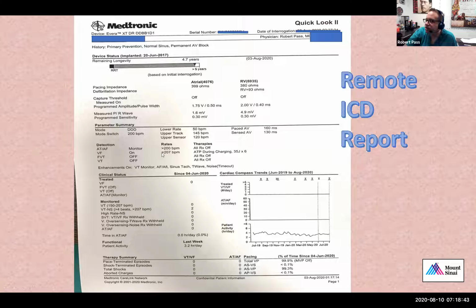But if the patient's heart rate exceeds 207 beats per minute, the device will try anti-tachycardia pacing, which is where the device will try to pace terminate the tachycardia. And it does that while it's charging. And if it doesn't work, it will shock the patient with 35 joules up to 6 times. Okay. And you can see there are different zones. There's a fast VT and a VT zone.